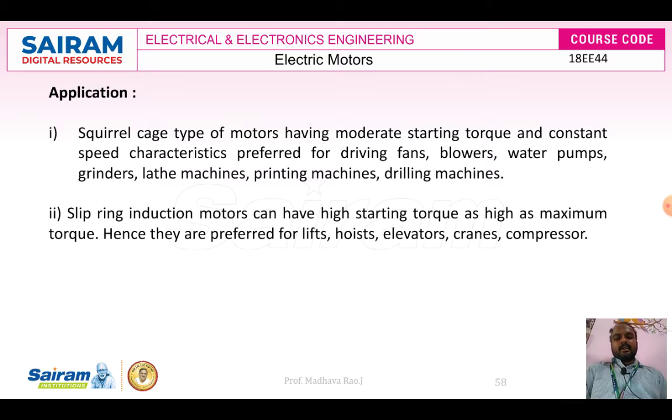Where we need to control the speed, so we need to increase or decrease the speed of the motor, in those cases we choose slip ring induction motors. Slip ring induction motor can have high starting torque since the resistance is high. So slip ring induction motor has high starting torque and high maximum torque.